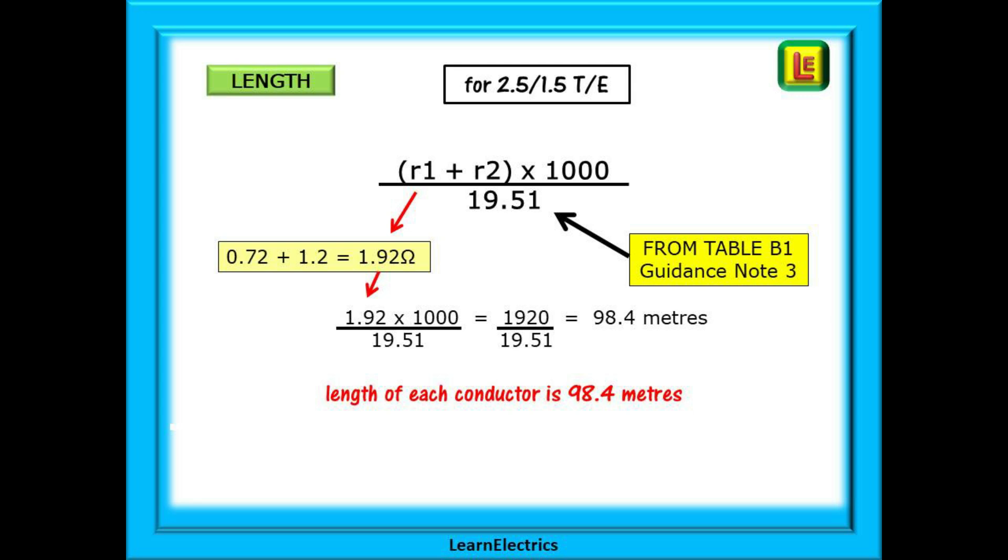Let's work it out. 0.72 plus 1.2 is 1.92 ohms. Multiply this by 1000, and we have 1920 divided by 19.51. Our twin and earth cable length is 98.4 metres end-to-end. Each conductor is approximately 98.4 metres long.